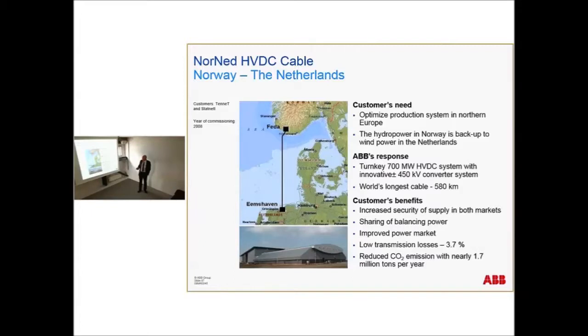Here it was to utilize the hydropower in Norway for peak power. They have also wind power connected, so when they have low demand and much wind generation, the power direction will be the opposite. So it's a trading line here, but the main power direction is from Norway to Netherlands. And the losses of the total system, including the converter station, are 3.7%, whereof the station has approximately 1.5%.